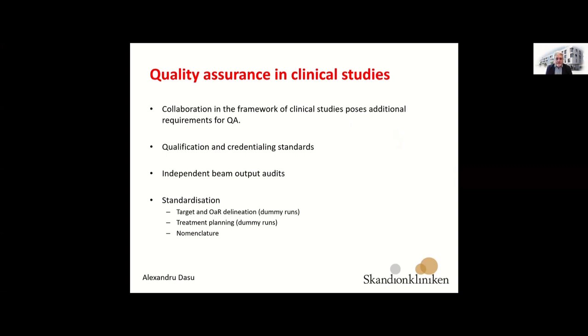Clinical studies. Nowadays, it's quite frequent that multiple clinics collaborate in the framework of clinical studies. And this poses additional requirements for quality assurance. An important part, for example, in order to get into a clinical study is the qualification and credentialing standards, where you have to, among other things, perform an independent beam output audit in order to prove that you could deliver the intended dose. This is actually something that should also be part of the general quality assurance program, because it checks the accuracy of your dosimetry system and could take out a systematic error that might have been overlooked.